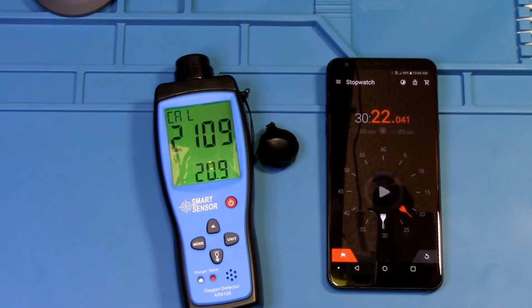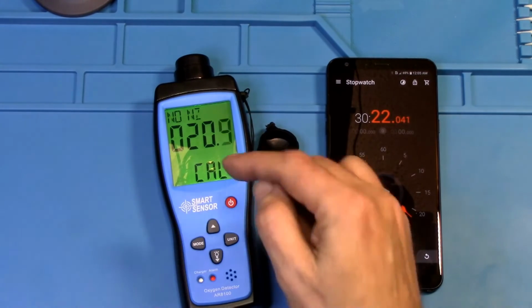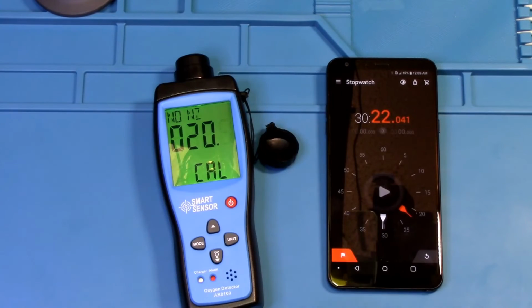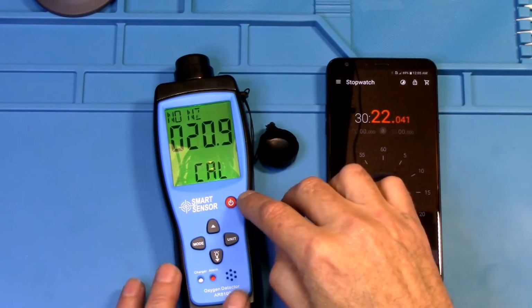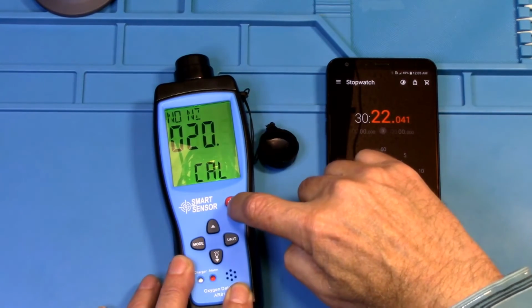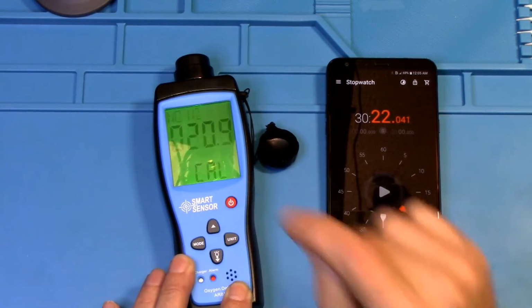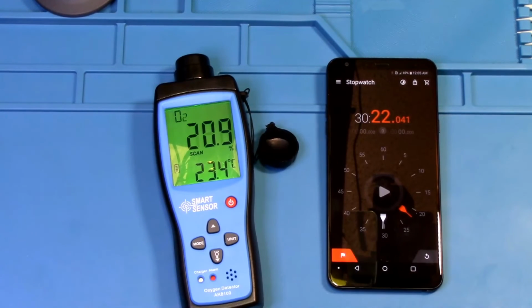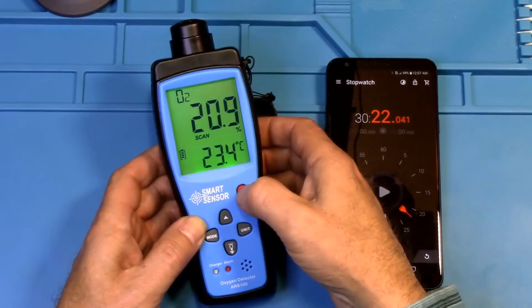Okay, I think it's pretty stable now. Once you've let it set for at least 30 minutes and it seems to be stabilized, only jumping around a few numbers at a time, then hit the mode button again real quick, and that will go back to the 20.9. Once it shows 20.9 again, then all you have to do is press the power button real quick to exit out of the calibration mode. And now it will be registering correctly.